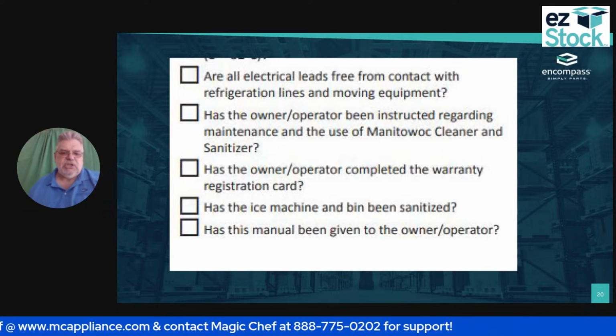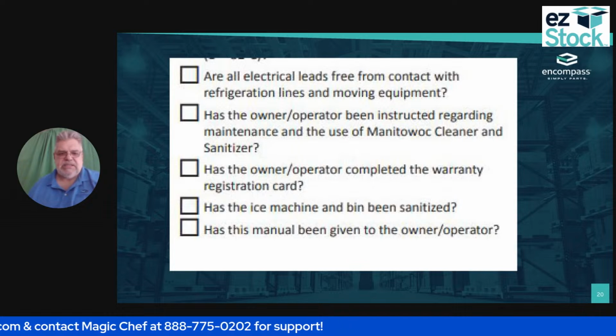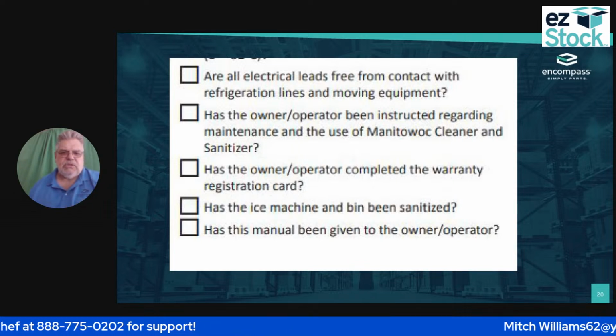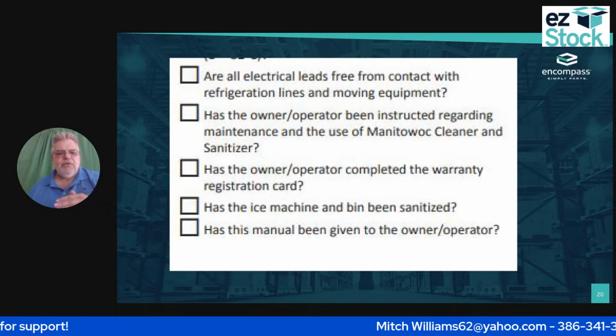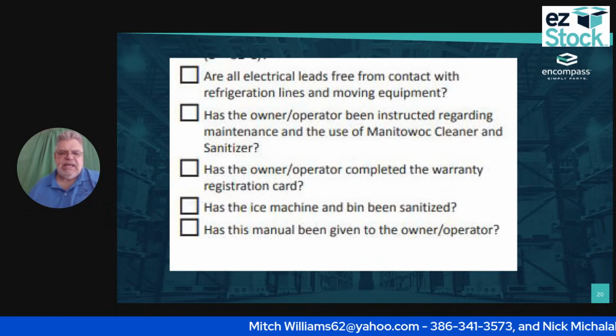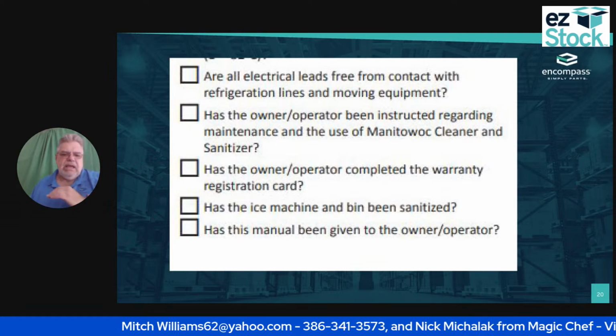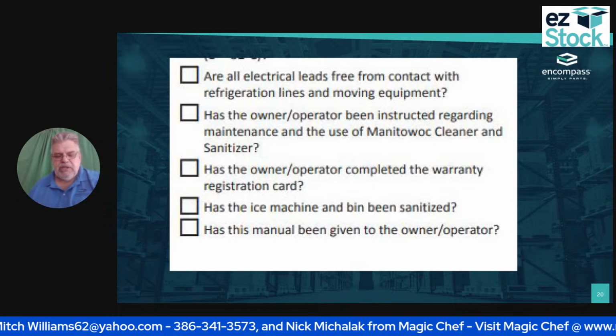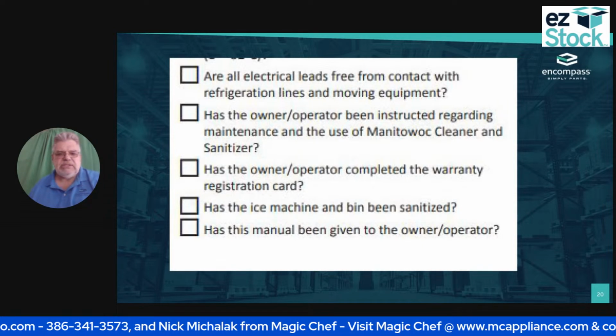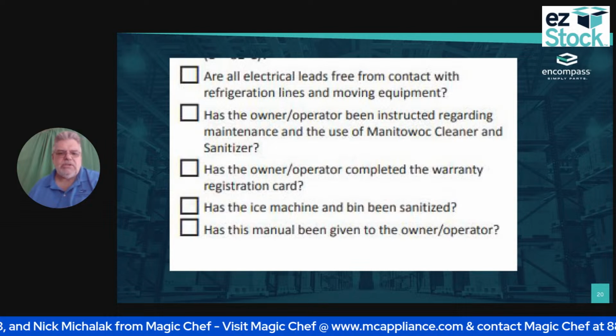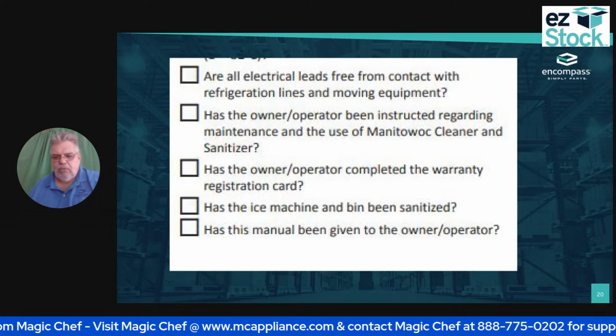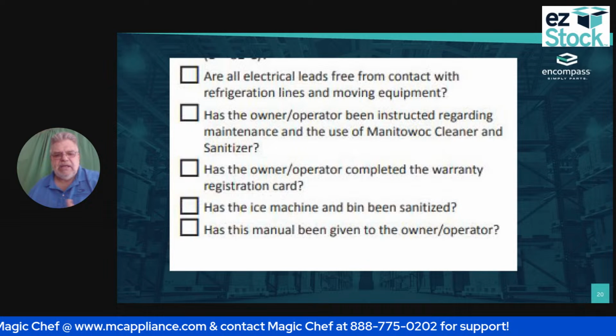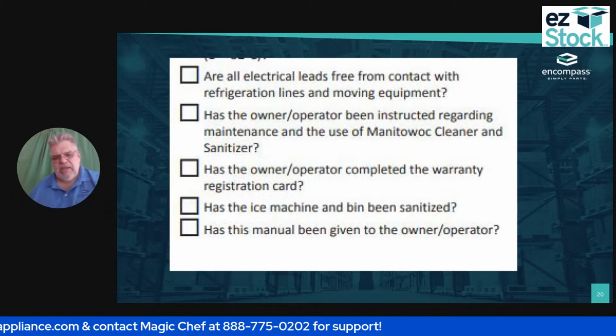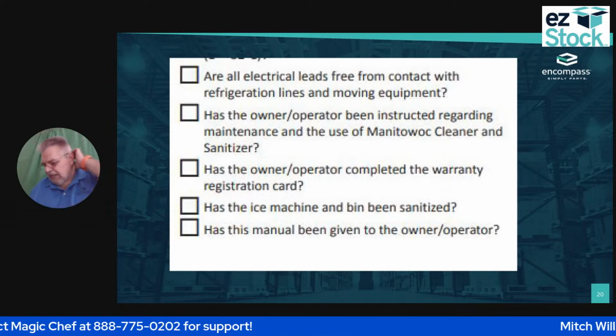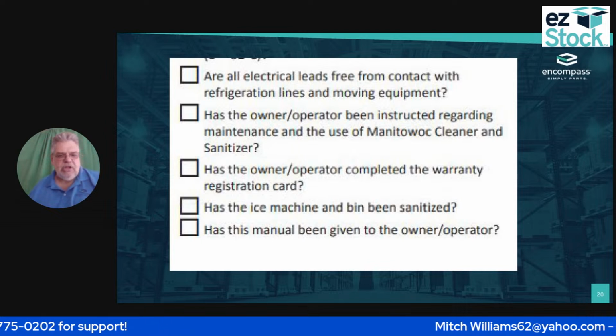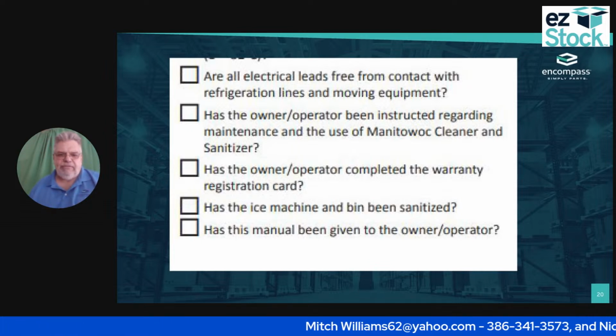Okay, has the ice machine and bin been sanitized? This is all part of the maintenance. If you don't clean and sanitize this bin probably every 6 months, the customer needs to do it at least once a month for the bin area, because everybody's got their hands all around the edges and on the top. You've got to keep all the sludge and slime off.